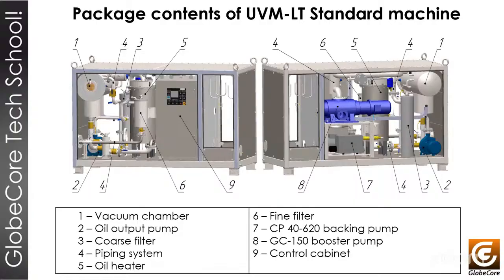Okay. Also, we will see different parts of this machine. You can see the different numbers are connected with a specific part in this slide. But one important thing is you will see number 8, the 150 booster pump. These UVM series machines have a special remark: a two-stage vacuum system, and you can see the booster at number 8. This is the pump that will greatly increase the vacuum level inside the machine, and that will make a really good performance of the machine when you need to dehydrate the oil and remove gases from the oil.